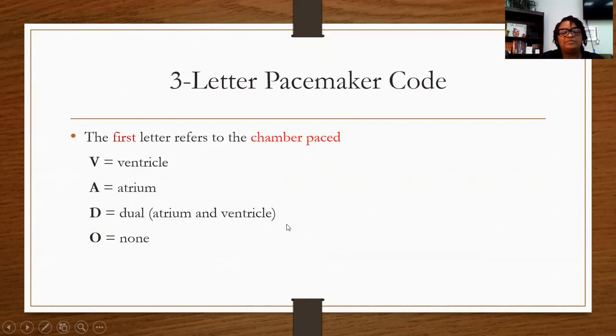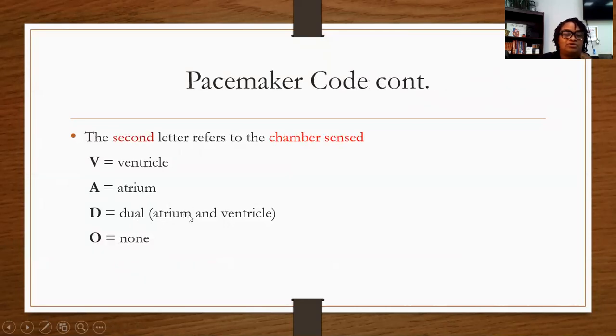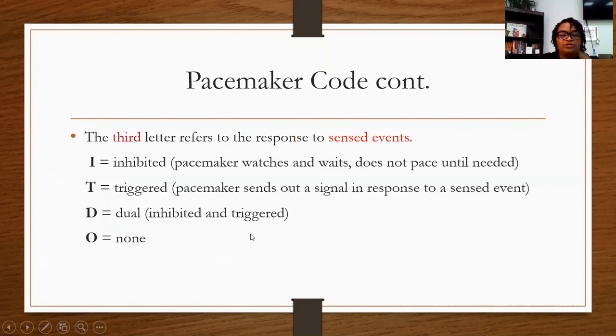So EKG pacemakers have their own code, okay? It's called a 3-letter pacemaker code. The first letter refers to the chamber that's being paced, whether it's the ventricle or the atrium or both, or none. Your second letter refers to the chamber being sensed, okay, whether it's the ventricle, atrium, both, or none. And then the third letter refers to the response to the sensed event. Did it inhibit the pacemaker from firing, in which the pacemaker watches and waits but does not pace until it's needed? Or was it triggered, in which the pacemaker sends out a signal in response to the sensed event? Or does it do both, or none?